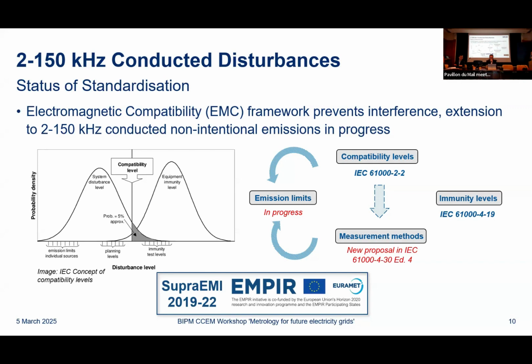Why is this important? Especially for harmonics, let's say up to 2 kilohertz, there is what we call an electromagnetic compatibility framework, and that makes sure that there's no interference. You've got your compatibility levels, the maximum acceptable level of disturbance in the grid. And then you've got immunity levels, so all the appliances, everybody who connects to the grid, has to tolerate that level of disturbance at least. Usually the immunity level is higher. And then you've got emission limits, and they limit what can actually be injected into the grid by individual appliances.